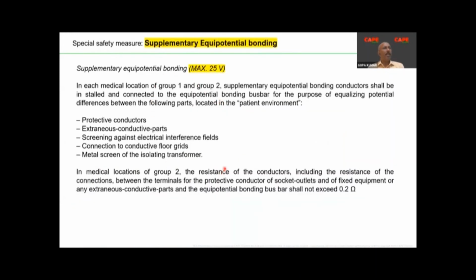The second subject in medical areas, and I'm not explaining all the points, only some of the important ones, is supplementary equipotential bonding. You must understand that the resistance of a person's body is offered by the skin. In a medical location, most of the time, biomedical equipment is bypassing the skin. As a result, the resistance is quite low, and even a small shock voltage could create a problem. So in these locations, supplementary equipotential bonding means, imagine a room with a lot of apparatus. The bodies of all those apparatus must be interconnected in such a way that between the equipment, the maximum resistance is 0.2 ohm. This is very much mandatory.